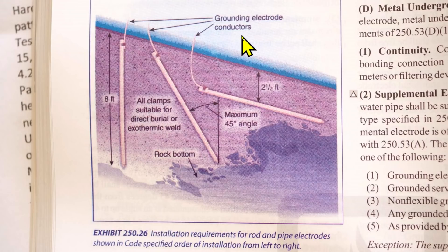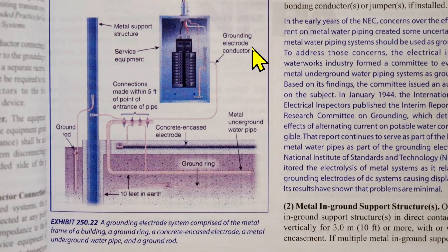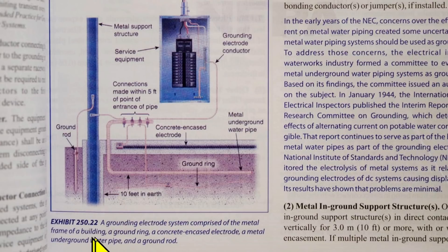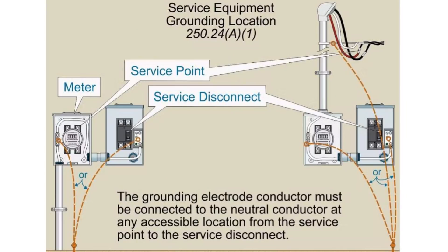So there's another example of a grounding electrode conductor. It says here installation requirements for rod and pipe electrodes. This is a good example of an electrode. Grounding electrode conductors — and here's another example. This is Exhibit 250.22 in the handbook. In this depiction, it says a grounding electrode system comprised of the metal frame of a building, a ground ring, a concrete encased electrode, a metal underground water pipe, and a ground rod — showing that you can have more than one type of grounding electrode. Terminating the GEC is covered in 250.24 A1.